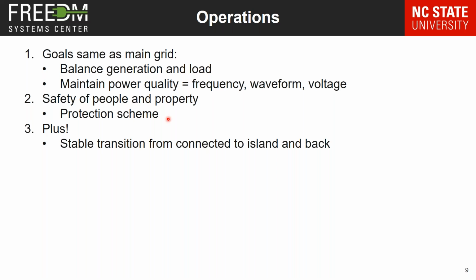Here's why microgrids can be complex: you're basically building a mini utility. You've got the same goals, you have to balance generation and load, maintain power quality including frequency and waveform, and regulate voltage on your system. You still have to provide the safety required by electrical codes, but you have to design your protection scheme for the microgrid—where do you put your breakers, do you need relays for the switches, do you need all these other pieces. This is where power systems engineers get involved in helping design these, and those are the kinds of things they consider, but it just shows how complicated it is.